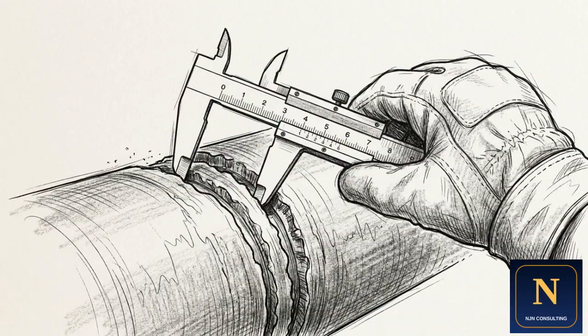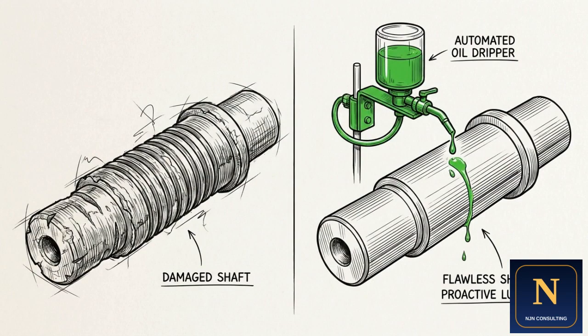For example, bearing failure due to contaminated lubricant. Finally, we record the visible effect that occurs when that failure happens. Pinning down that specific physical root cause is the mandatory first step. You can only assign an effective, proactive maintenance tactic once you know exactly what mechanism you are trying to prevent.